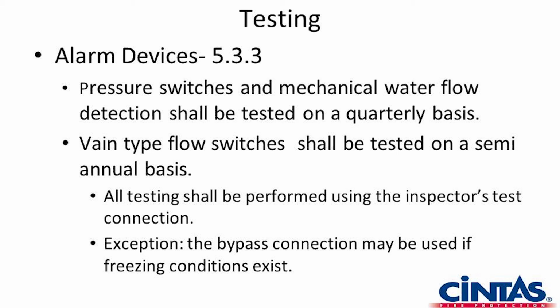If we put those on a dry system, what they found years ago, and I can't even remember a time when it was ever allowed, so it must have been some very early testing. When the dry system trips, pipes shake. You can feel it. You can hear it. It's just an inrush of water. It was tearing those nylon discs off of the flow switch.